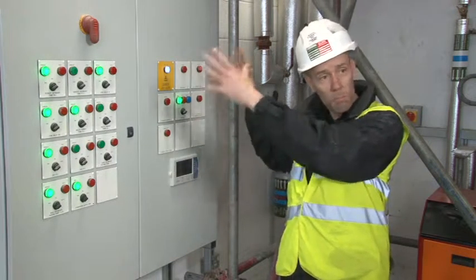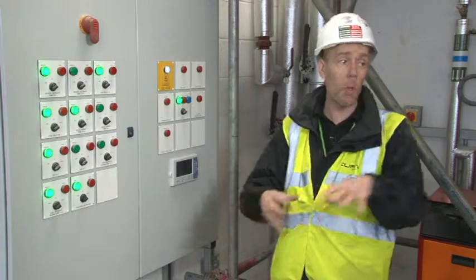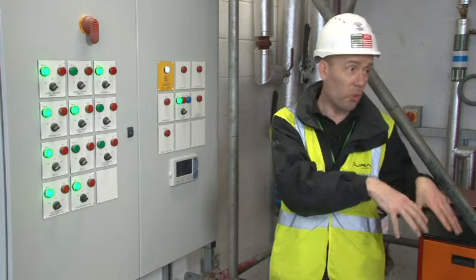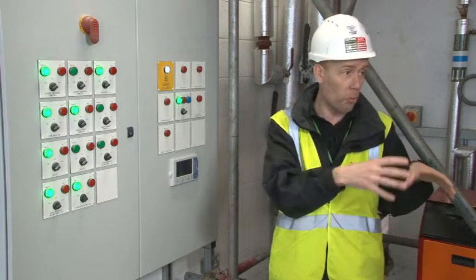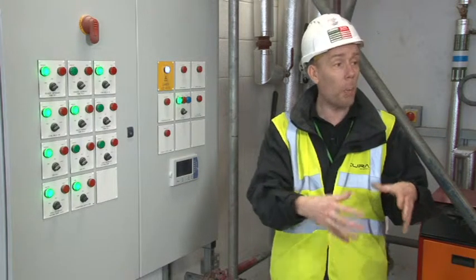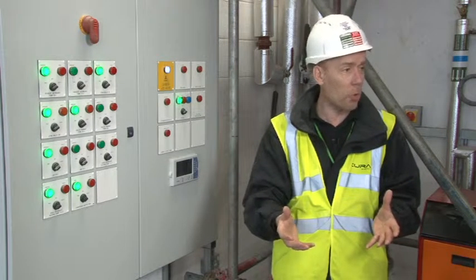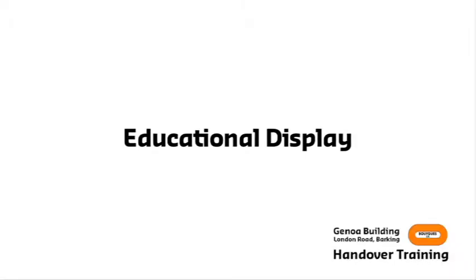This is the functioning end, the hardware end. There's a software end, which is the concierge's monitoring of those alarms and noticing that it's in alarm and that he needs to get an engineer out to come and have a look at the faults.